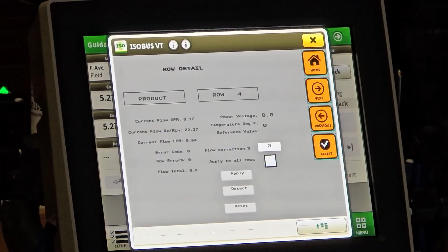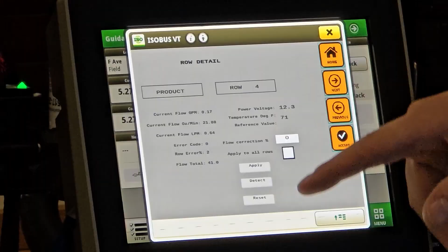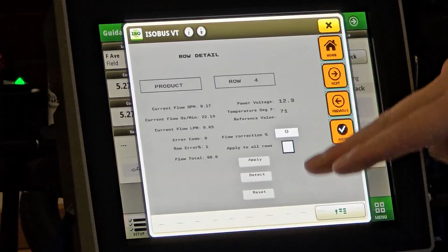So now that I'm locking in on rate, you can see that all the colors are towards the center, so I know I'm locking in on rate. If I were to tap on a row 4 here, I can see what my flow rate is. With this, here I have the ability to change the calibration of that one sensor per row. So each flow meter, even though it monitors 4 rows here, there's still an individual sensor for each flow meter that's in here. And then I can have my percentage offset for each flow meter.